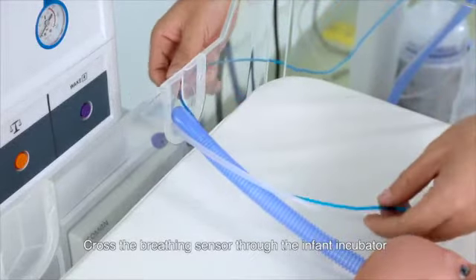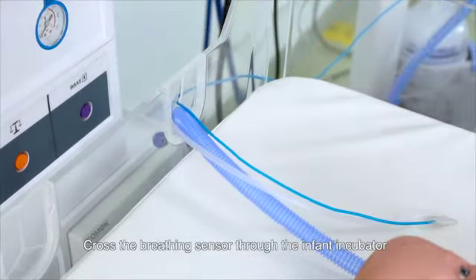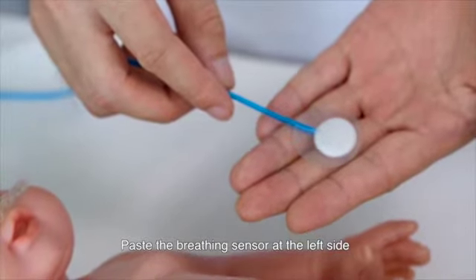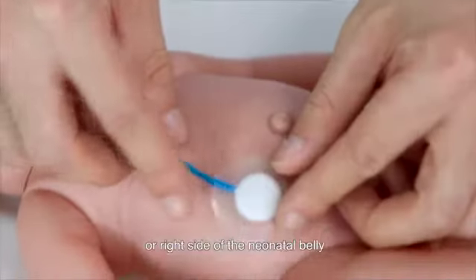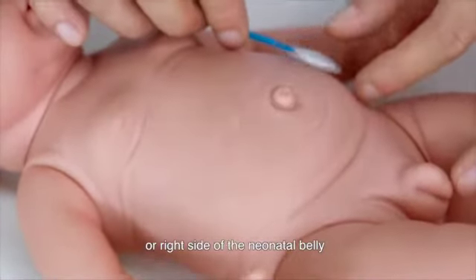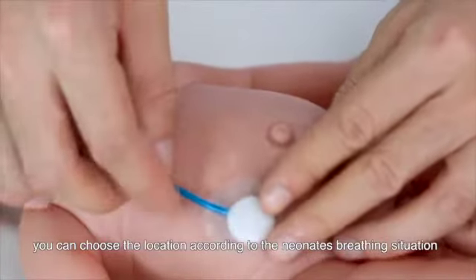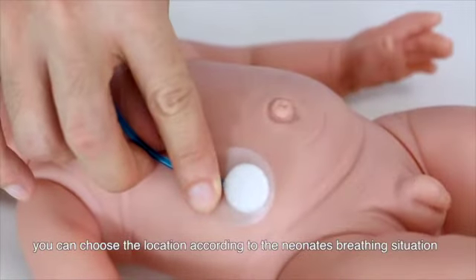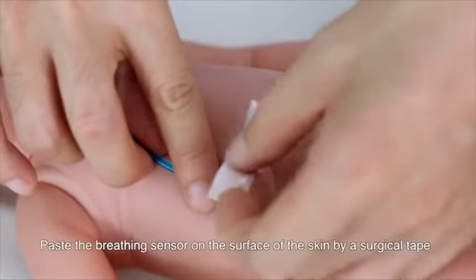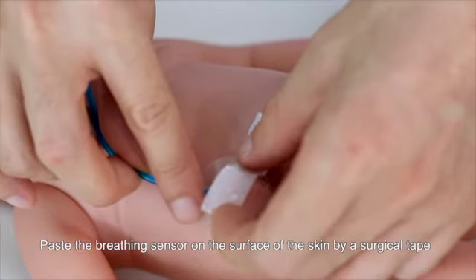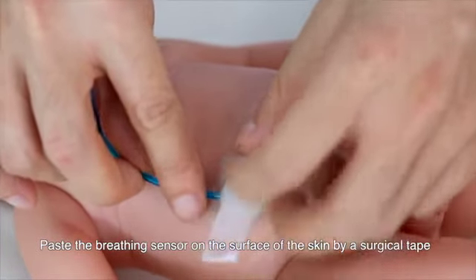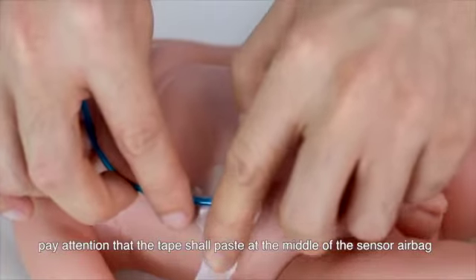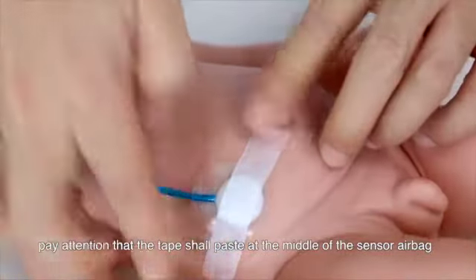Cross the breathing sensor through the infant incubator. Place the breathing sensor at the left side or right side of the neonatal belly. You can choose the location according to the neonate's breathing situation. Place the breathing sensor on the surface of the skin with surgical tape. Pay attention that the tape shall be pasted at the middle of the sensor airbag.